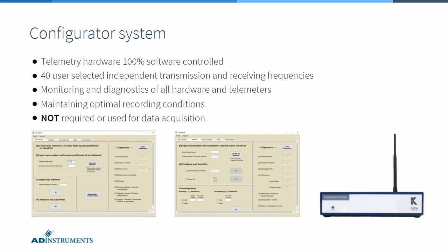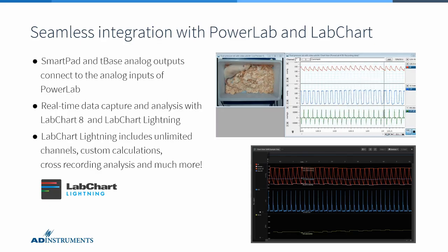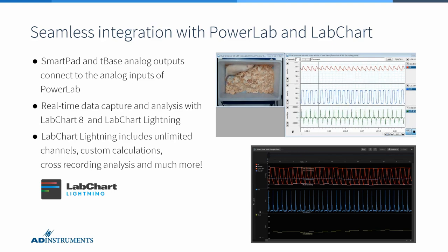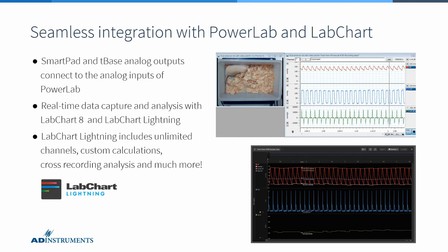It's worth pointing out that this is not a data acquisition system. It's not required for data acquisition. It's solely for the control and the configuration of the telemetry system. Data acquisition is provided by the PowerLab data acquisition hardware and LabChart software from ADInstruments.